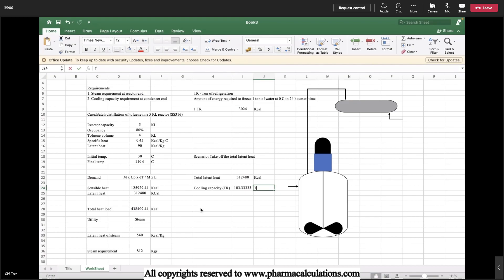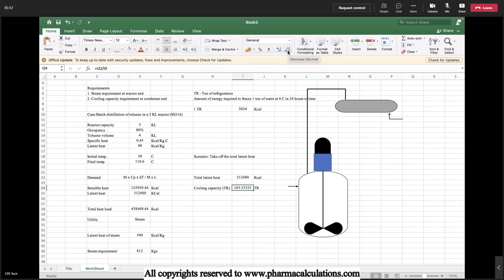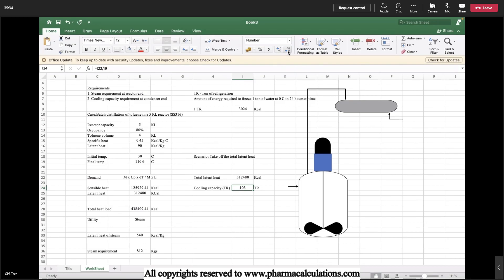That means we need total of 103.3 TR, approximately 104 TR. But coming to the practical case, a condenser is going to perform sensible heat transfer also. That is the vapor is going to reach at 110.6 degrees centigrade, and after immediate condensation the temperature of the liquid is going to be at 110.6 degrees only.